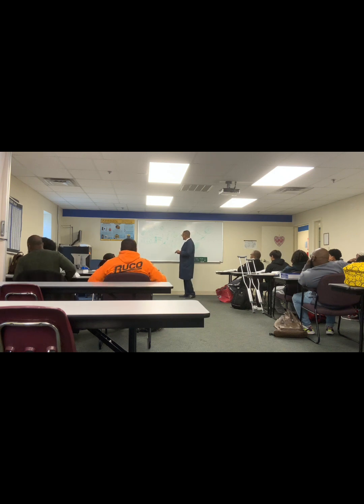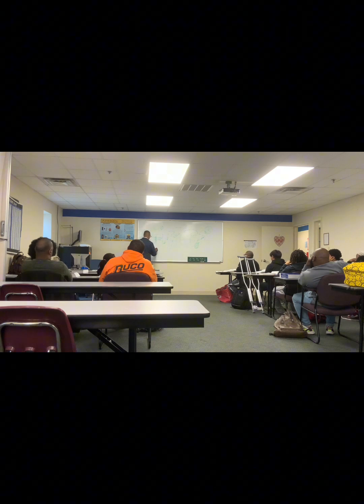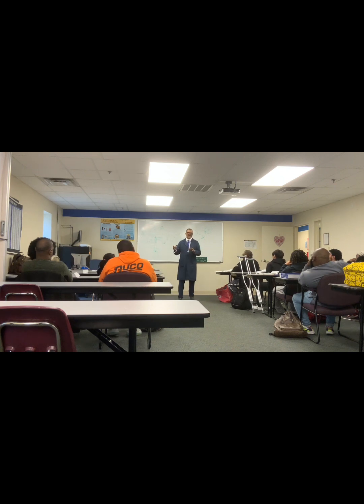And what does that mean? So for instance, if you were on a furnace and you had a vent pipe right here, you really want it to go straight up to the roof. Isn't that the quickest, most clear route? However, what if I was right here and it's going up to the roof right there? So sometimes you have to change the route, and you might have to put a 90, and then when you use one 90, you usually have to use two, because you've got to get back to where you were.